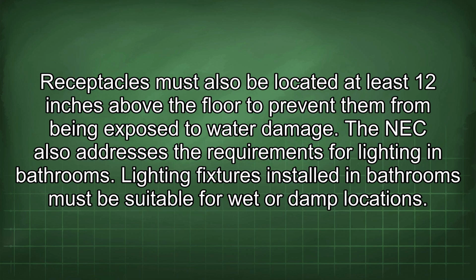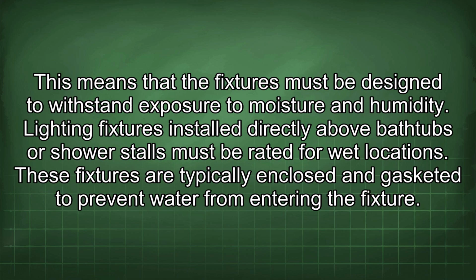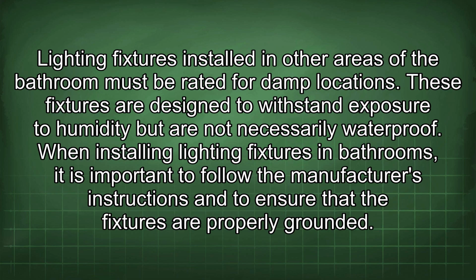The NEC also addresses the requirements for lighting in bathrooms. Lighting fixtures installed in bathrooms must be suitable for wet or damp locations. This means that the fixtures must be designed to withstand exposure to moisture and humidity. Lighting fixtures installed directly above bathtubs or shower stalls must be rated for wet locations. These fixtures are typically enclosed and gasketed to prevent water from entering the fixture. Lighting fixtures installed in other areas of the bathroom must be rated for damp locations. These fixtures are designed to withstand exposure to humidity but are not necessarily waterproof.